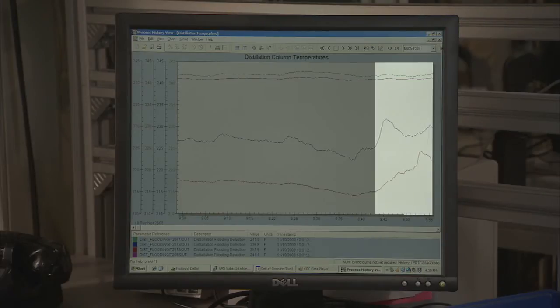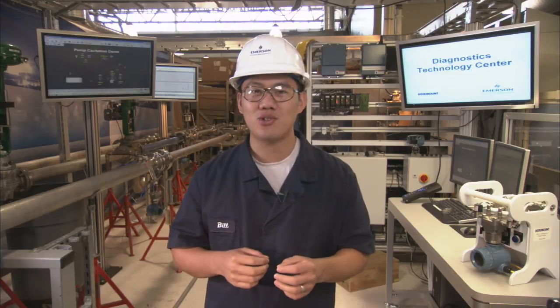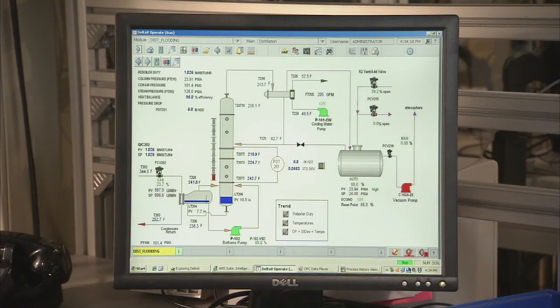The 3051S is not only a high-performance pressure transmitter, but it can also measure and perform statistical process calculations based on the process noise. As the column begins to flood, there is a step change in this process variability. This changes the standard deviation and delivers an early warning of an impending flooding condition. Here, we can see that the 3051S has triggered an alert notifying the operator that flooding may have started.